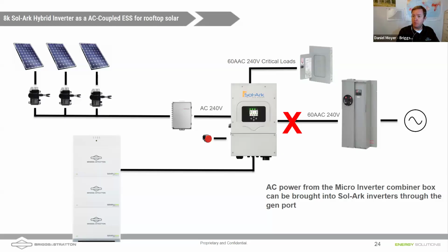And with the 120% rule out of the NEC, usually it's a 40 amp breaker, unless you derate the main maybe, or upgrade to a 225 bus bar. What's interesting about a lot of these newer inverters is the PCS control, or the ability so that it can always draw 60 amps, but using the controls inside the inverter, it will never send back more than 40 amps, so you don't overload that bus bar.